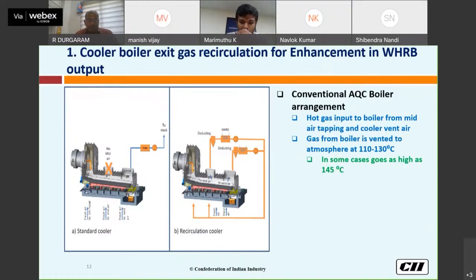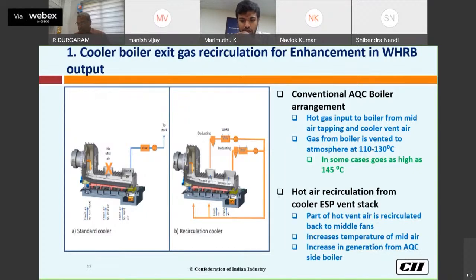Now I'm going to give a brief on what happens with recirculation and without recirculation, and how it helps. For example, in a conventional AQC boiler arrangement, hot gas is input to the boiler from the mid-air of the cooler, and the gas from the boiler is vented at around 100 or 130. If you bypass some amount of air, it will sometimes be 145 also. In the recirculation cooler, part of the hot air from the stack, after the ESP, is recirculated to the middle fan of the cooler, where our tapping is taken for the WHRB.